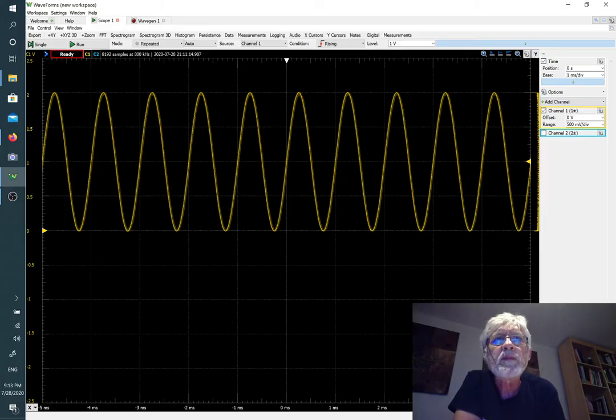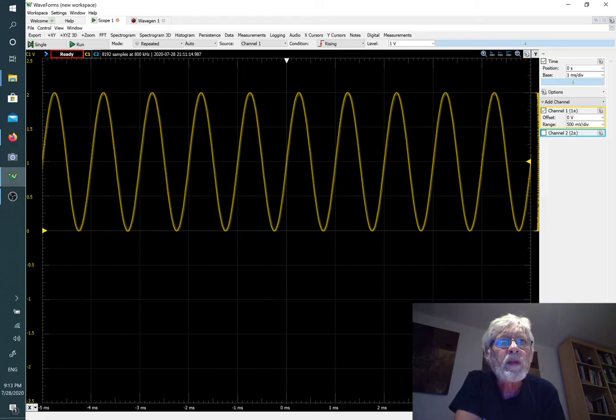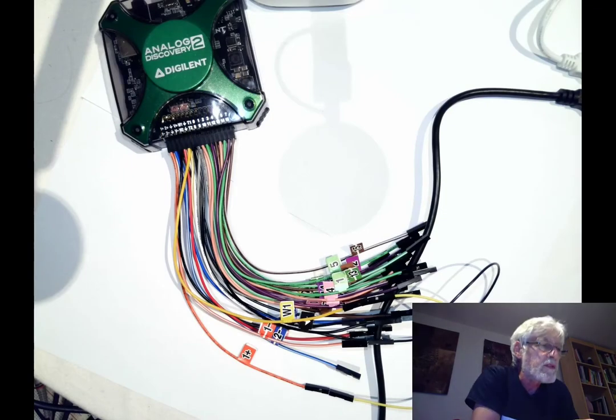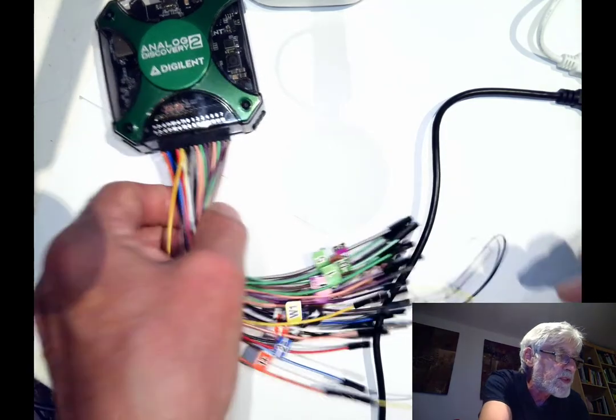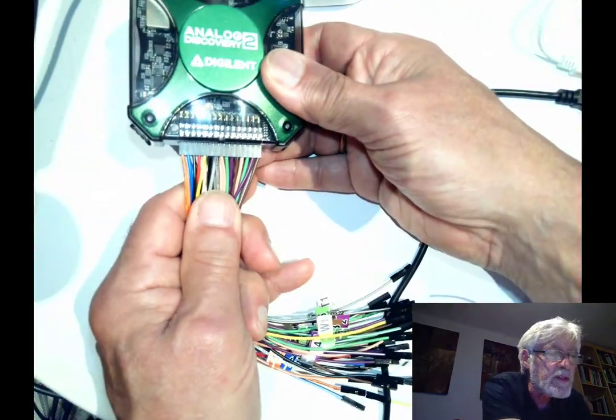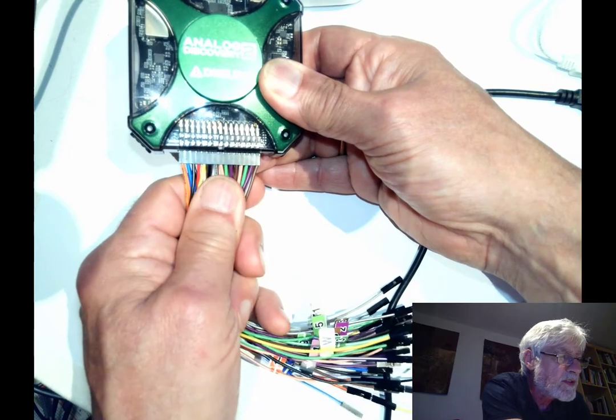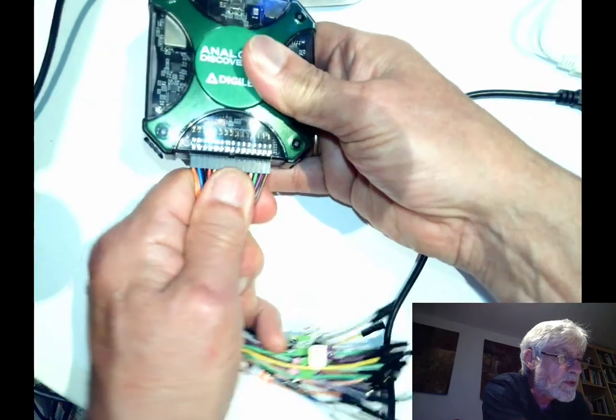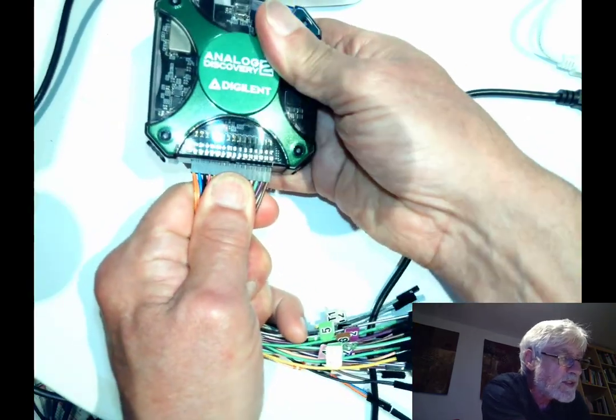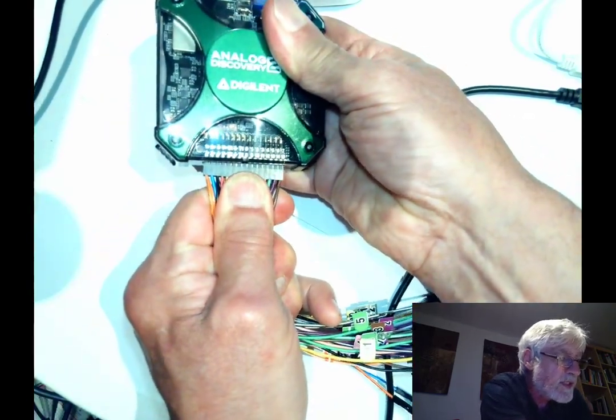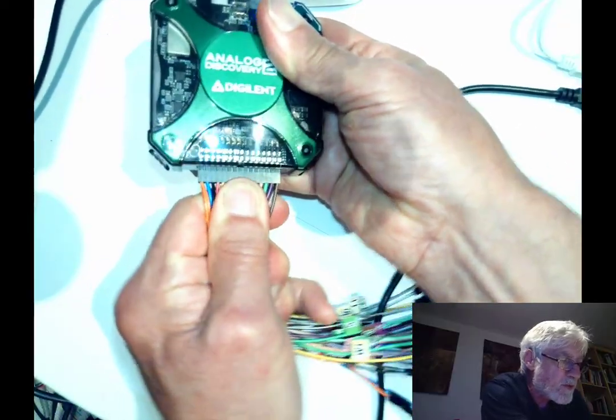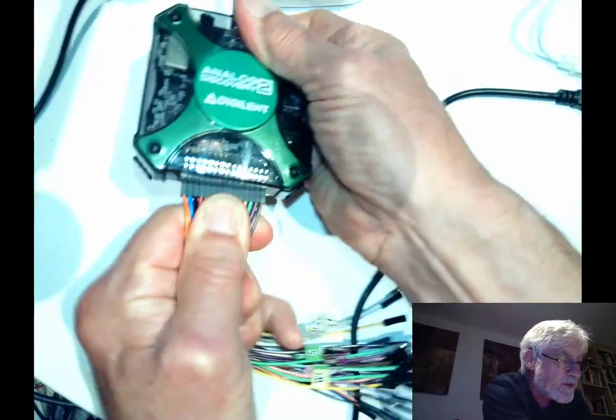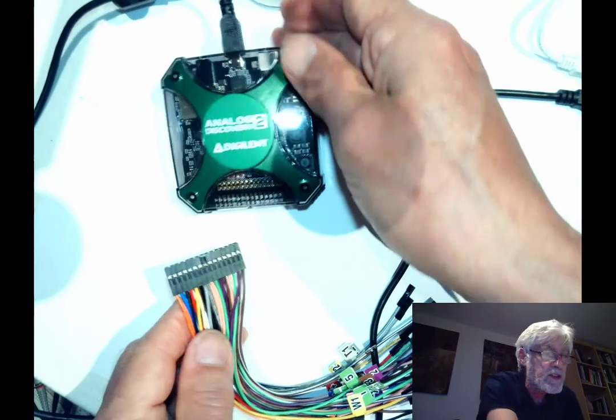What still needs to be done is we're going to take off the flywire assembly to give a demonstration of how that works. You have to hold all of the wires together and then pull on it. Don't just pull on a single wire, that might damage it. Then you wiggle it back and forth and pull it out of the 30-pin connector.